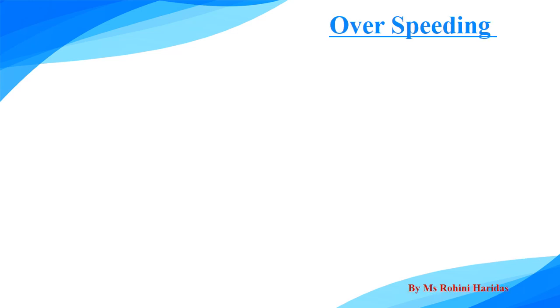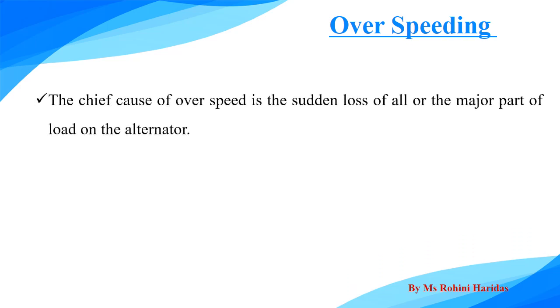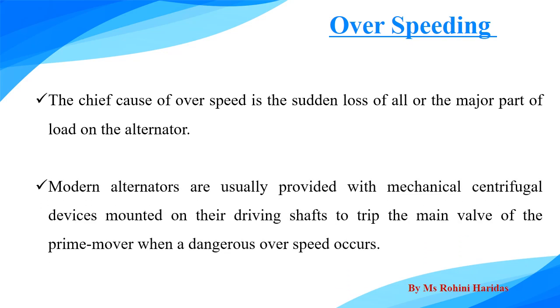And the last abnormal condition is the overspeeding. The chief cause of the overspeed is the sudden loss of all or the major part of the load on the alternator. The modern alternators are usually provided with mechanical centrifugal devices mounted on their driving shaft to trip the main valve of the prime mover when dangerous overspeed occurs.